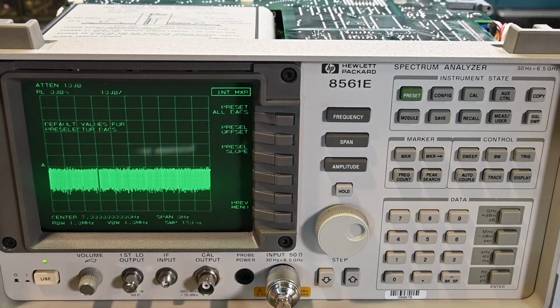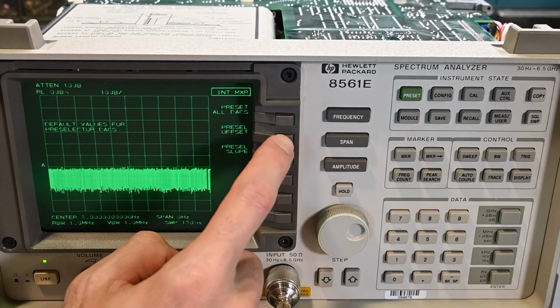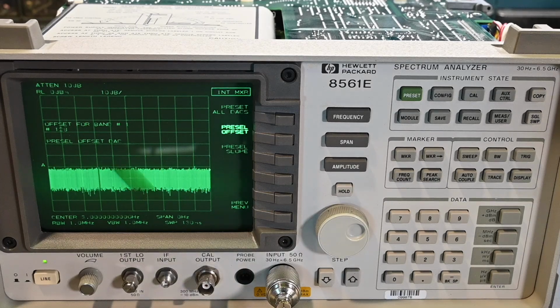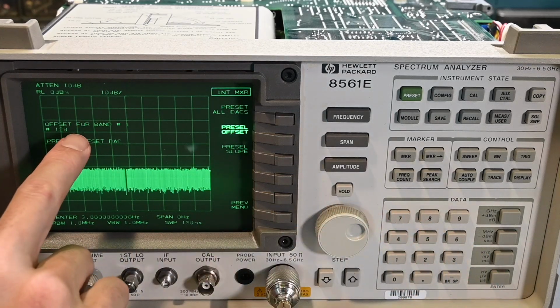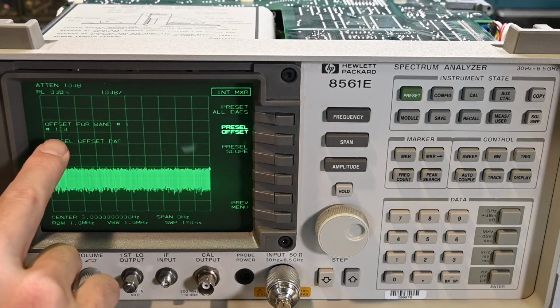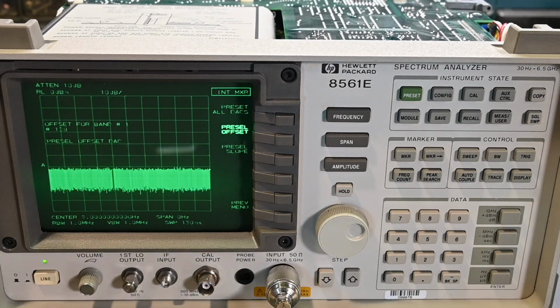Okay. All right, so then it just reminds us to have the signal generator at 3 gigahertz, minus 10 dBm. So everything is set on that. It says press pre-select offset. So it's this right here. Use the front panel knob to peak the displayed trace and record the offset DAC value below. All right, so we'll grab a pen here and, okay. So right here it says offset for band number 1, which is the high band, and it's currently set for 128, so that's again just an arbitrary value.